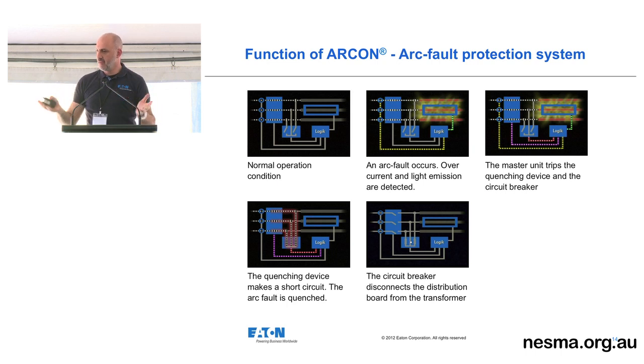To find out where the fault occurred, once that is eliminated, the board is still operable. When we talk about arc fault protection, yes, human life is the major principal factor in all this. The other part that people don't realise is that most boards that experience an arc fault are inoperable afterwards, so that's downtime. The replacement is lengthy. This one just needs a check, basically a visual check. Maybe if there's areas that need to be cleaned on the bus bar, the board's ready to go again.